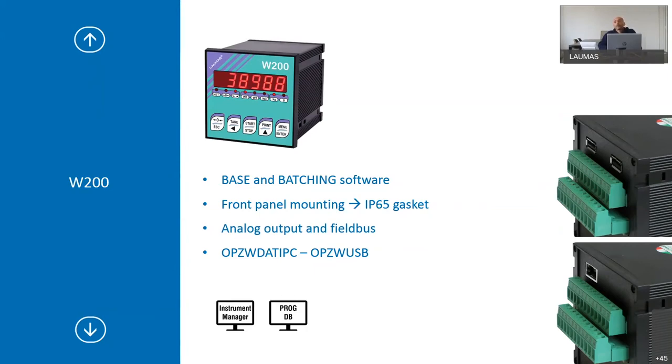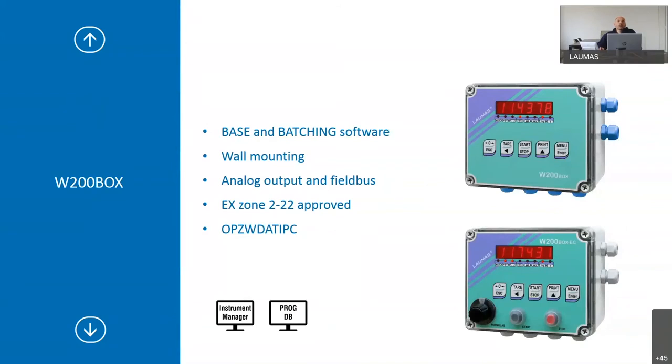W200 will have both record options. W200 Box is IP67 waterproof grade, but if you need external start/stop buttons and a formula selector, it is IP64. It follows the same rules as the W200: base and batching software, wall mounting, analog output and field buses available. The ATEX version is for EX Zone 2-22. In this case only the PC record option is available because USB cannot be installed.